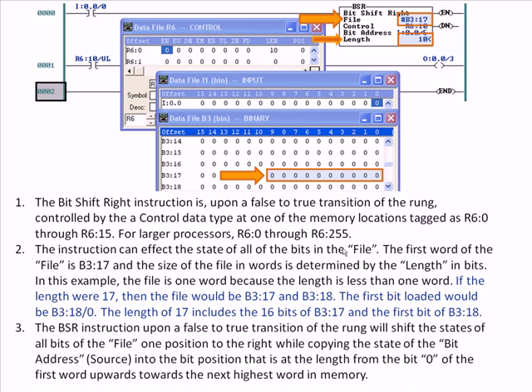With B3:17 and a length of 10, you're still working with bits 0 through 9. The BSR instruction, on a false-to-true transition of the rung, will shift the states of all the bits in the file one position to the right, while copying the state of the bit address — the source, which in this case is Input 5 — into the bit position at the length from bit 0 of the first word upwards toward the next highest word memory.